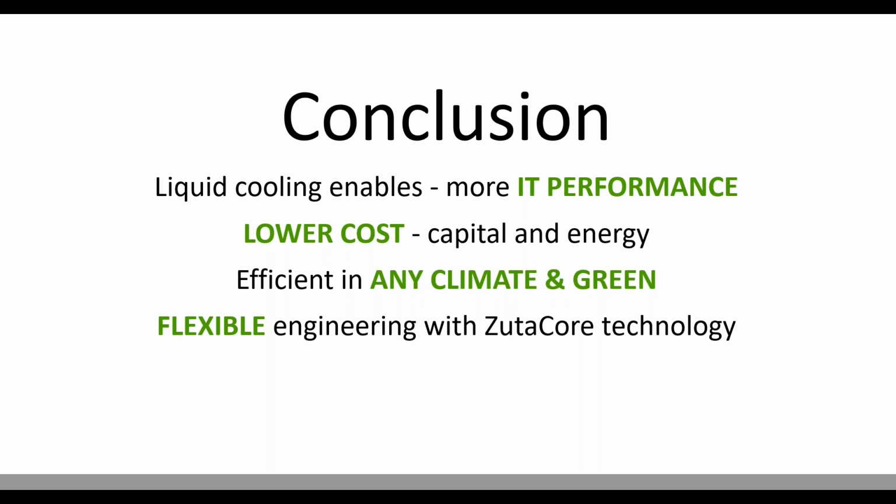But in this case, we're talking about trying to achieve very high density solutions directly at the chip. And I don't know if, when the tier 4 redundancy levels were developed, they really had direct-to-chip cooling solutions in mind. So maybe as the Uptime Institute looks further at direct-to-chip liquid cooling, there will be some revised guidance relative to the tier levels for that type of scenario.